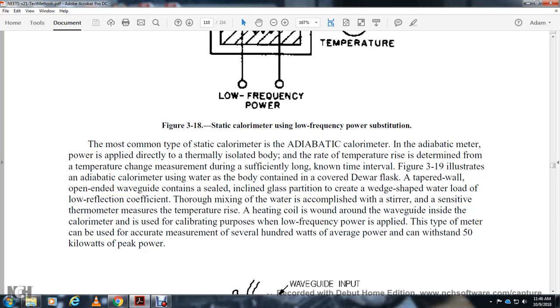A tapered wall at one end of the waveguide contains a sealed inclined glass partition to create a wedge-shaped water load of low reflection coefficient. Through mixing, the water is stirred and a sensitive thermometer measures the temperature rise. The heating coils are wound around the waveguide inside the calorimeter, and for calibration, low frequency power is applied. This type of meter can accurately measure several hundred watts of average power and can withstand 50 kilowatts of peak power.